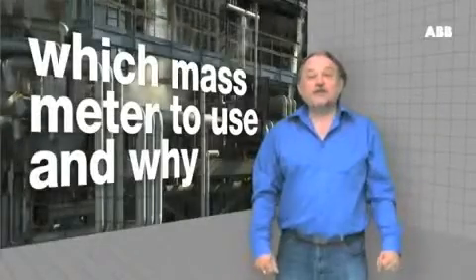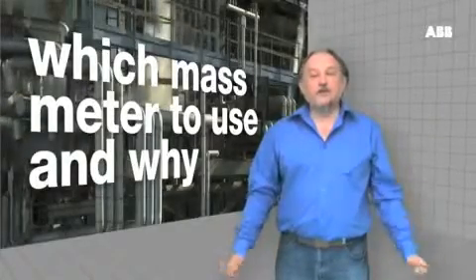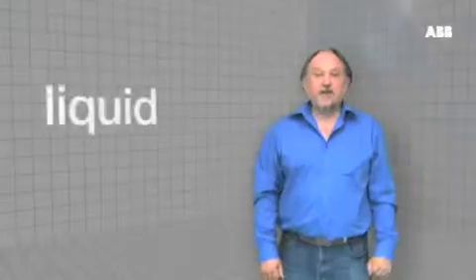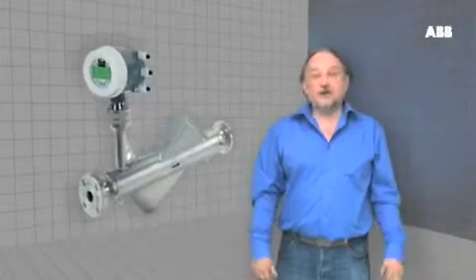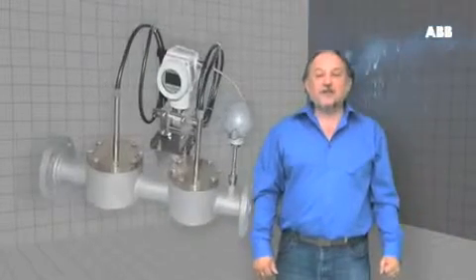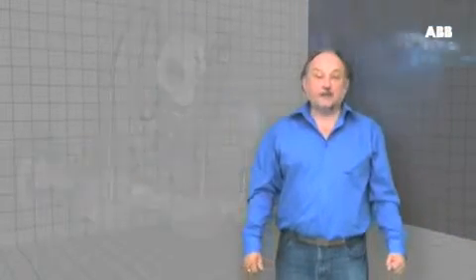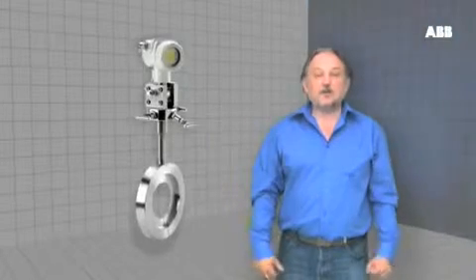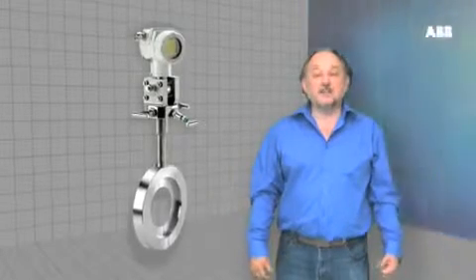In summary, this is what you need to remember about mass meters for various applications. For liquid mass flow measurements, especially where variations in product density are common and the product is priced by weight, Coriolis meters should always be considered. Their high accuracy and repeatability means excellent cost savings, and because product density can be measured, the quality of the product or its identity can be assessed.